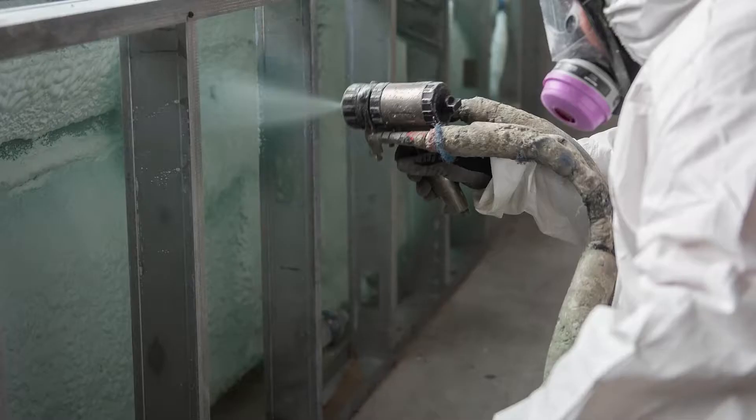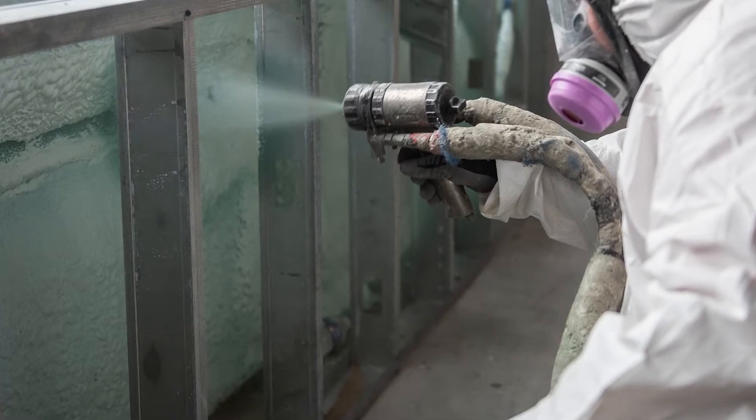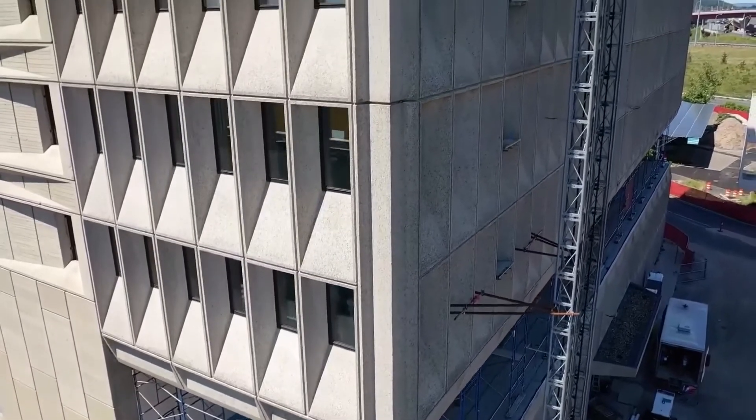For passive house, we're looking for the small air leakage that adds up across the whole building. So we actually do pressurization as well as depressurization, and we do interim component testing of the windows on the building.